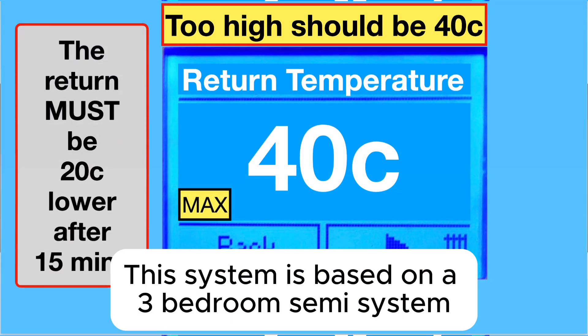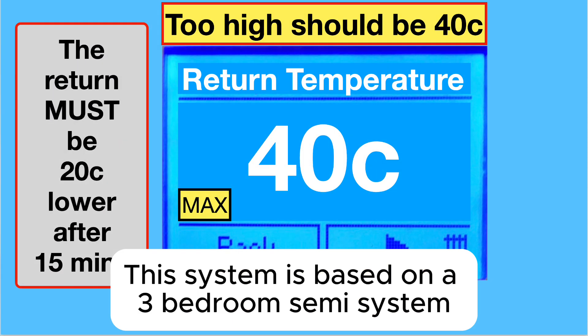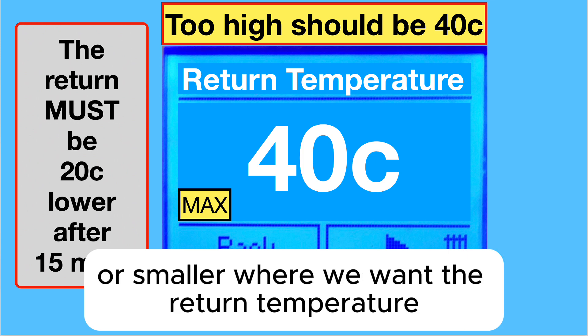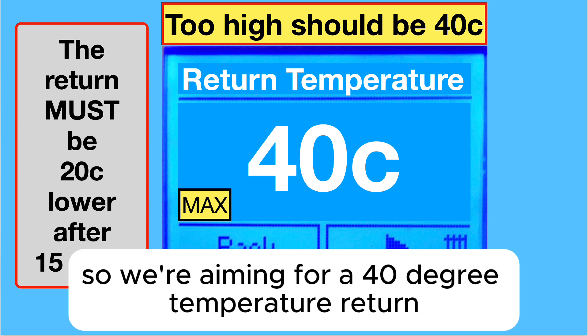This system is based on a three-bedroom semi-system or smaller, where we want the return temperature to be 20 degrees lower than the flow. So we're aiming for a 40 degree return temperature.